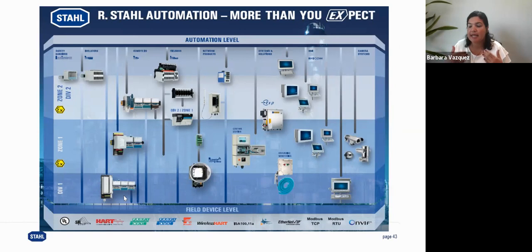So they exist above the field device level and below the automation level, which will be the controller, the PLC, the DCS. And we do have a lot of intrinsic safety in our portfolio. You can see here we have the Zener barriers that Ramin was talking about. We have the Galvanic isolator barriers. We have Remote IO, which has built-in barriers for intrinsic safety.